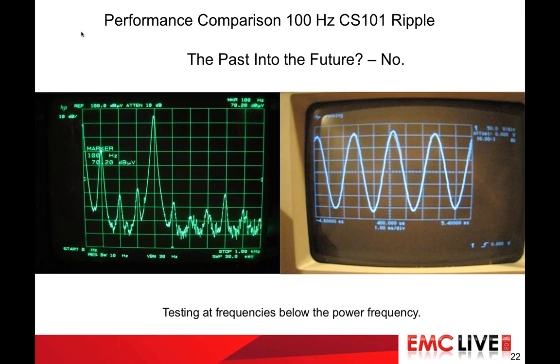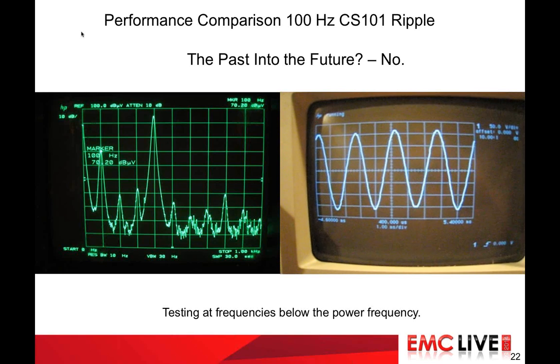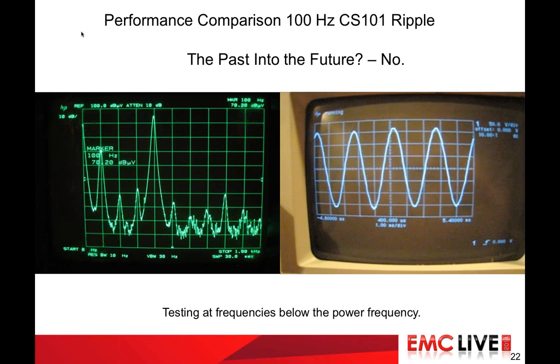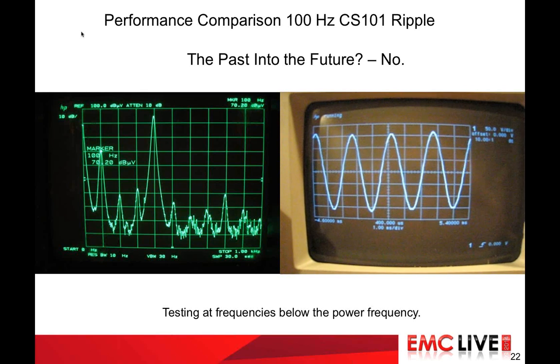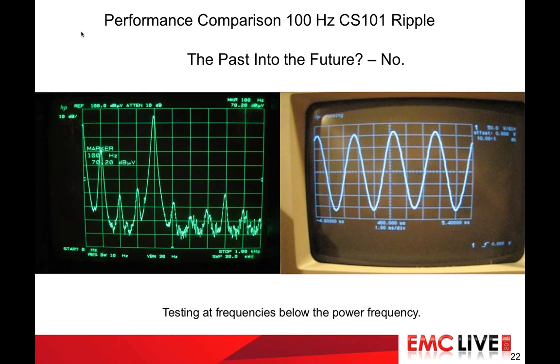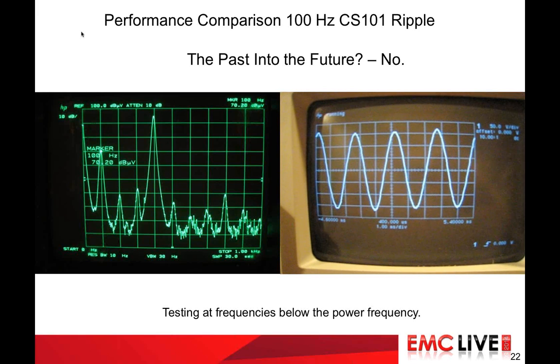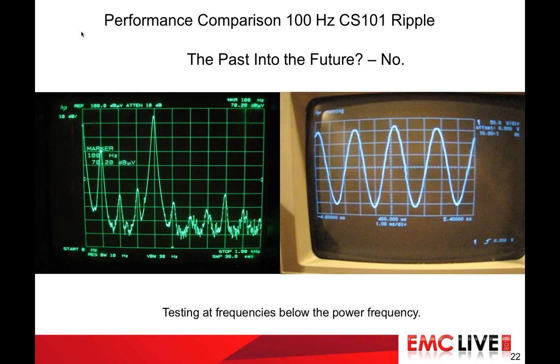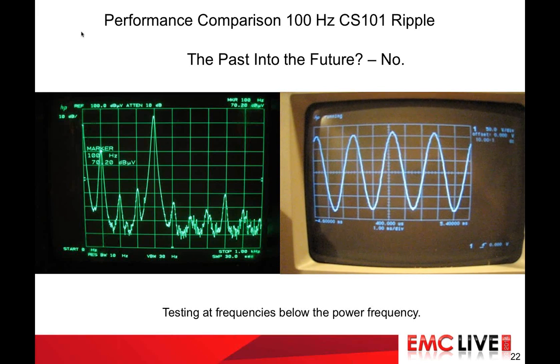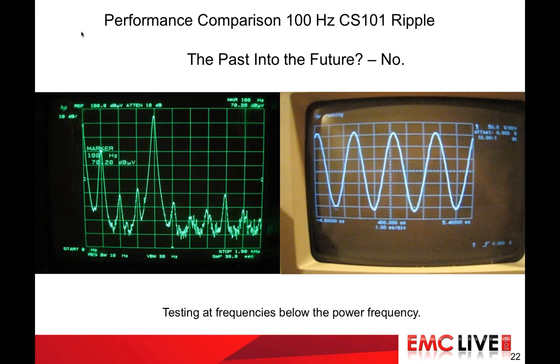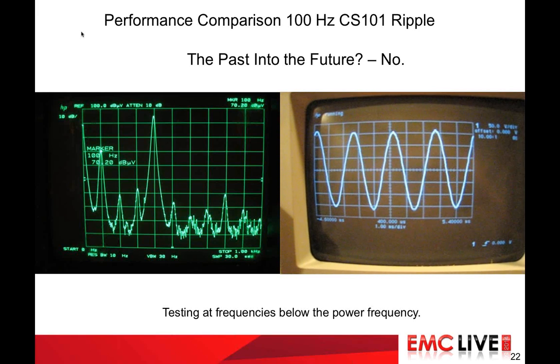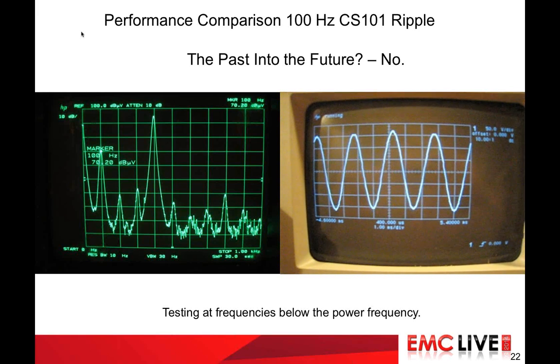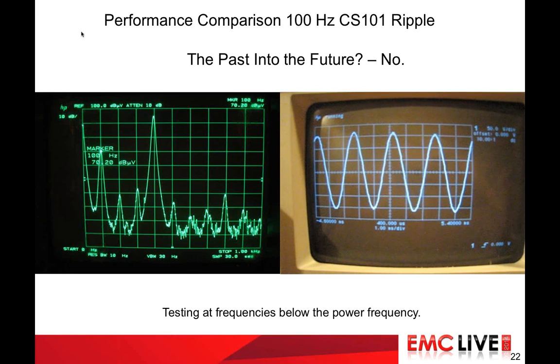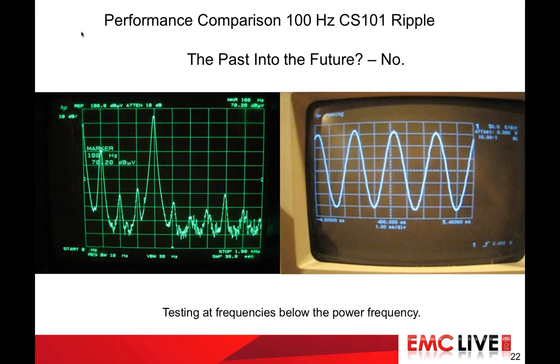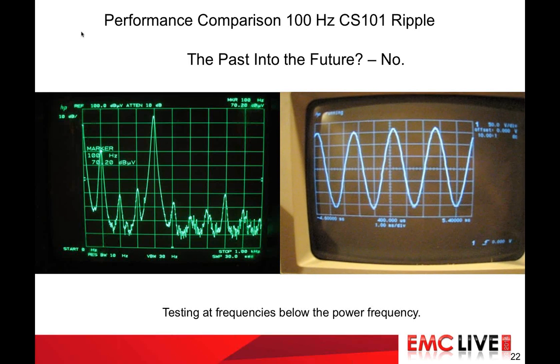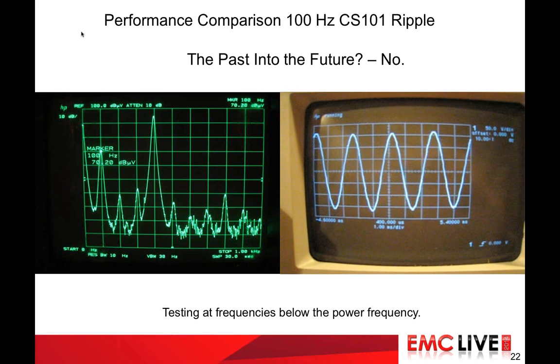Now, prior to 1993, the CS01 frequency range was 30 Hertz to 50 kilohertz, regardless of whether applied power was AC or DC. After 1993, that is after MIL standard 462D was adopted, use of the Solar Electronics 7021-1 phase shift network was forbidden, and as a result, it was impossible to monitor ripple injected at frequencies below the power frequency. The power line ripple detector makes it possible once again to monitor below the power frequency, and it is just as easy and no different than at frequencies above the power frequency.